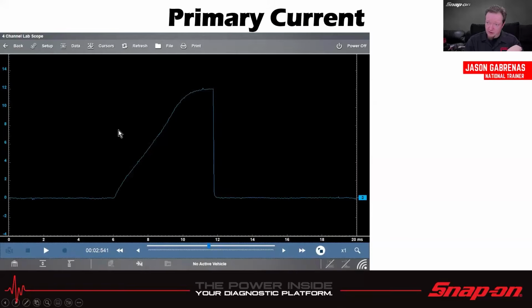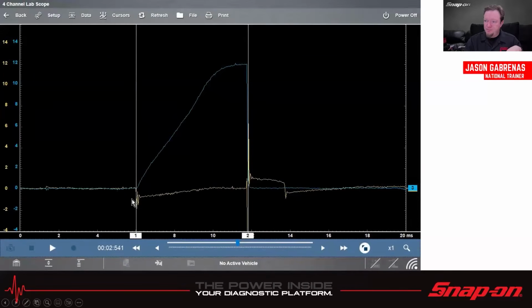If it goes up very sharply and then over, that could indicate an issue inside the windings in there. It's got a lot of resistance to overcome before it starts flowing current through there. And then here it is overlaid with our secondary, right?